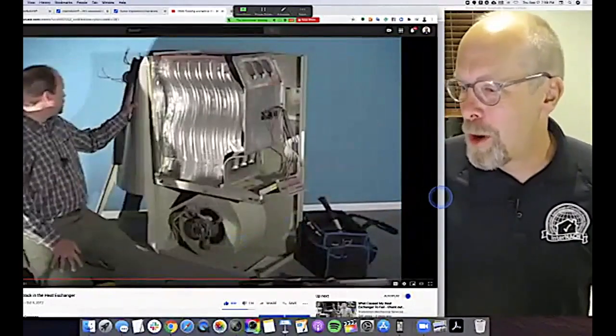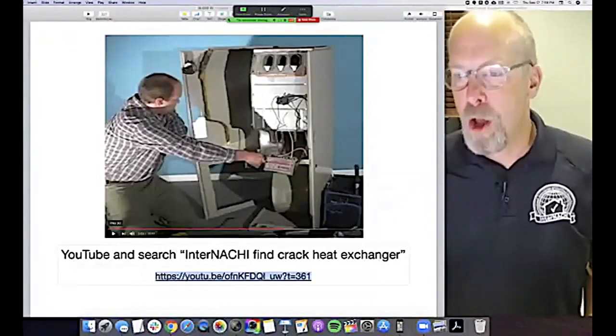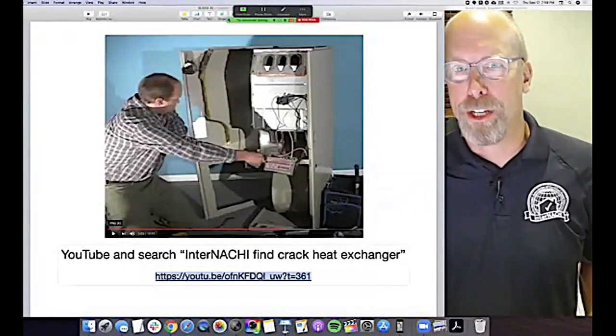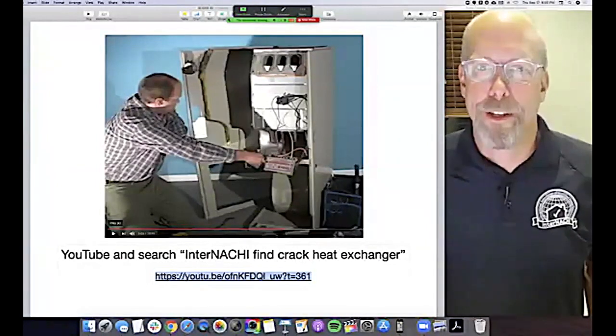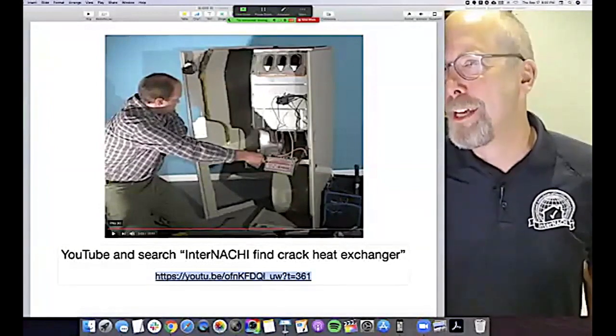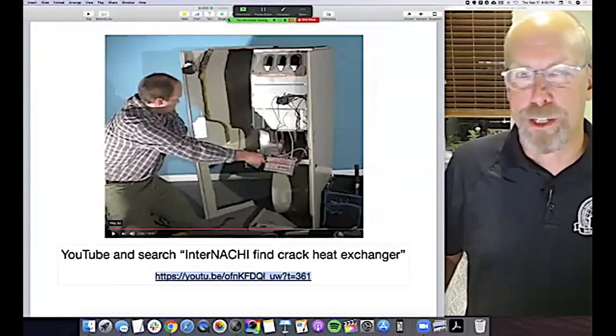So I wanted to show in that video, we have all kinds of training videos and articles and things like that, how impossible it is for a home inspector to find a crack in a heat exchanger. It's impossible. I tear open a gas-fired heating system right there. You can't find it. Don't worry about cracked heat exchangers. They've been talking about home inspectors and cracked heat exchangers for 20 years.